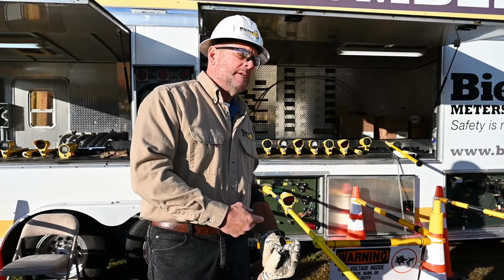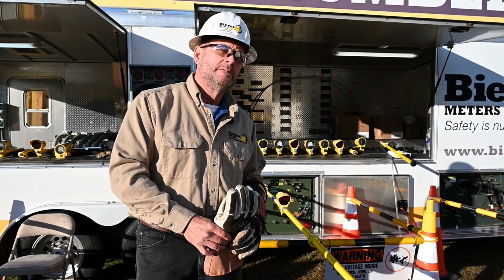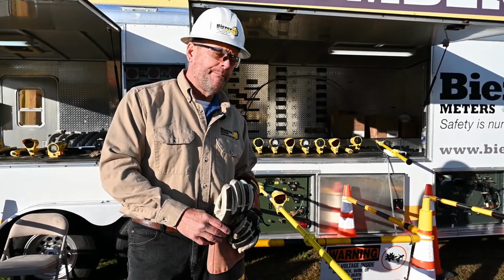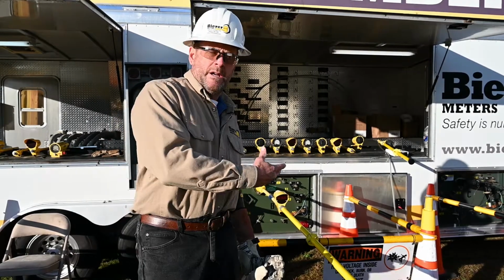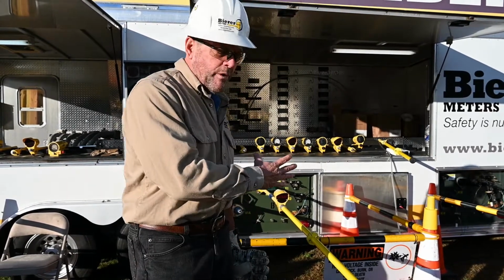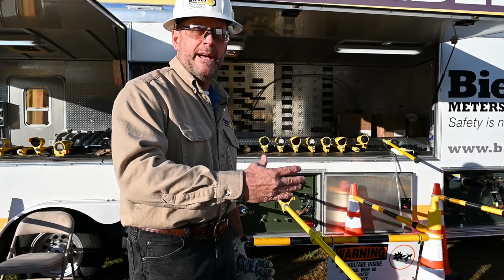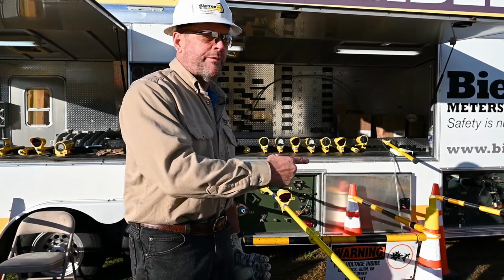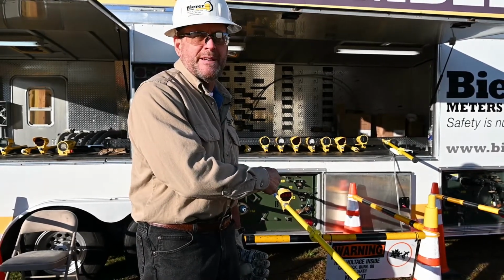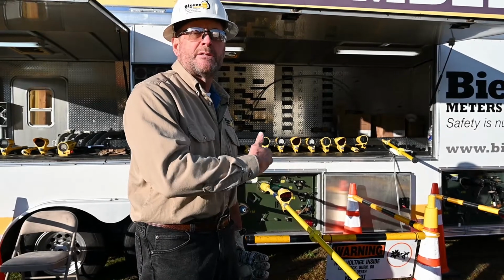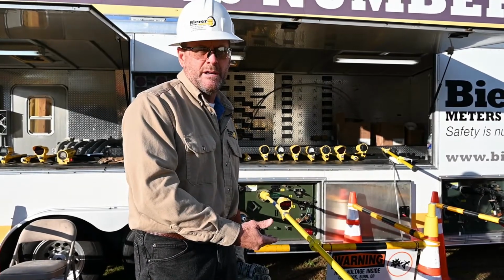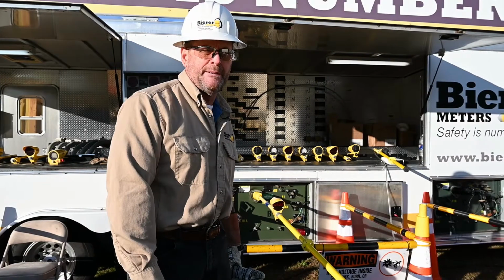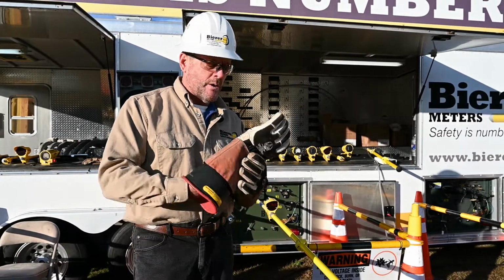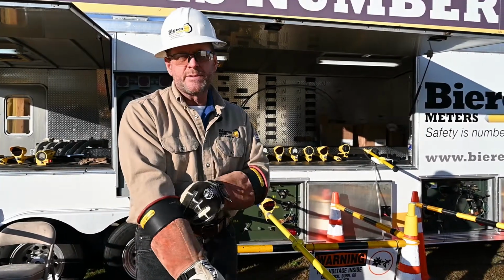So two things have taken place: we're further from the source with the meter head, and the meter head is further from the potential ground plane. So the meter is going to be more accurate for us. You all see that? A lot more accurate. So it's important that you use a zero ohm extension.